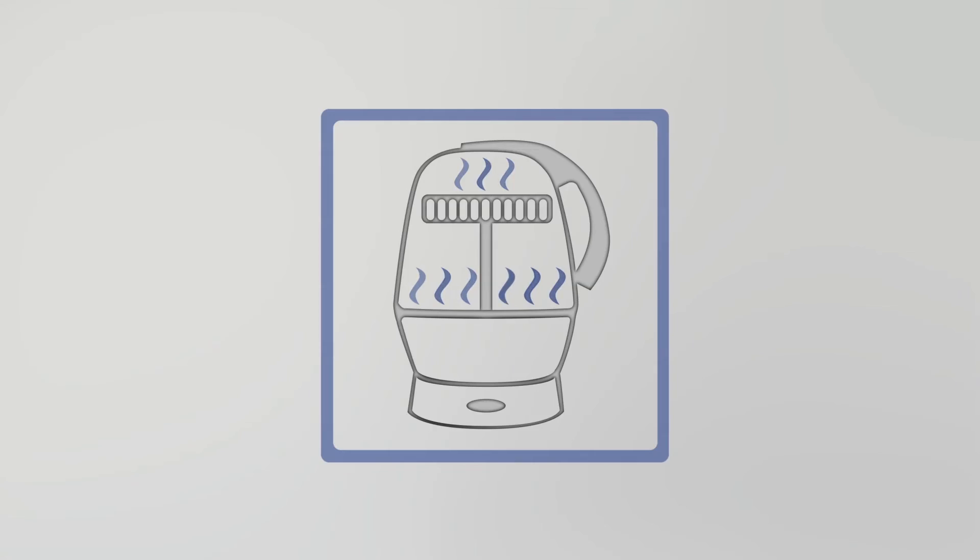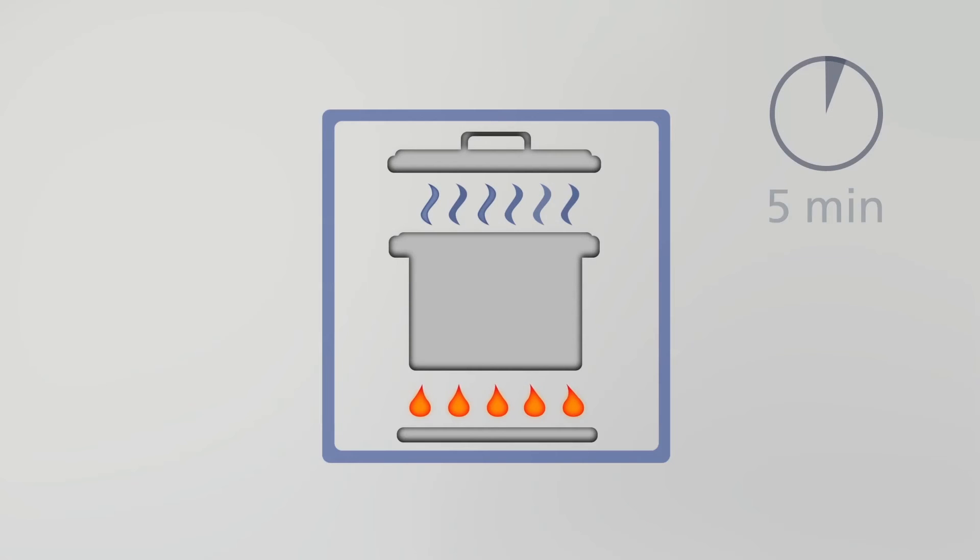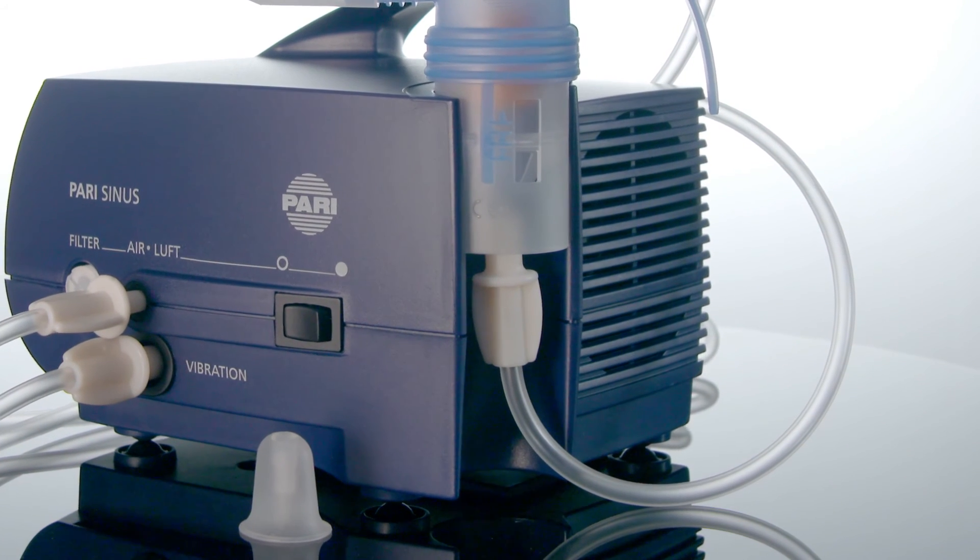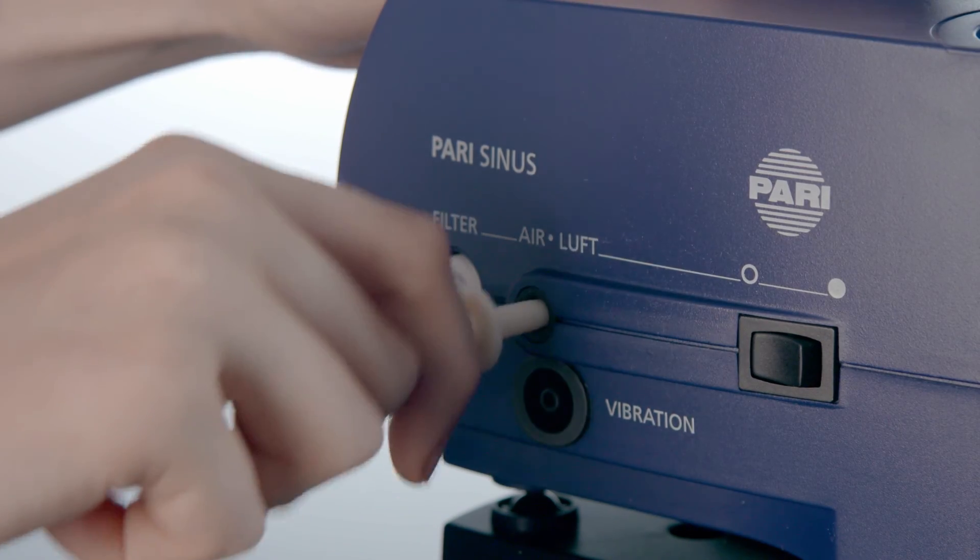The nebulizer should be disinfected once a week. A thermal disinfector can be used, such as a baby bottle disinfector. If preferred, the component parts of the nebulizer can be boiled for five minutes.